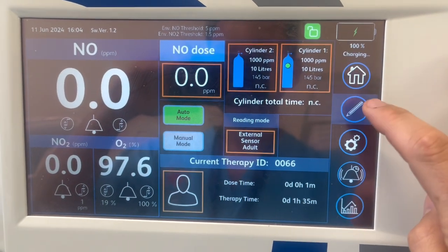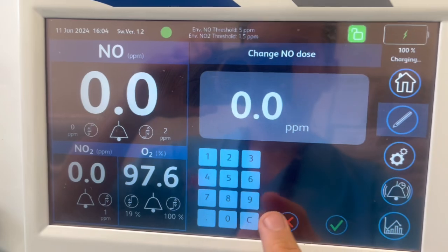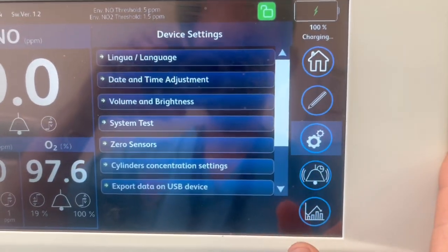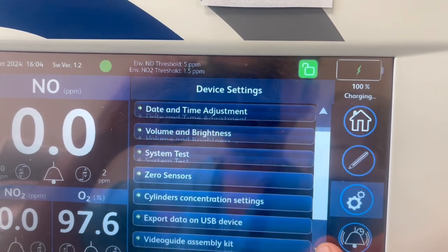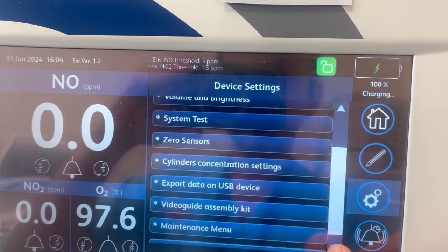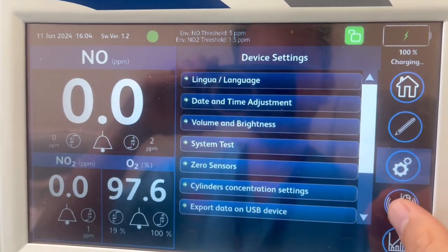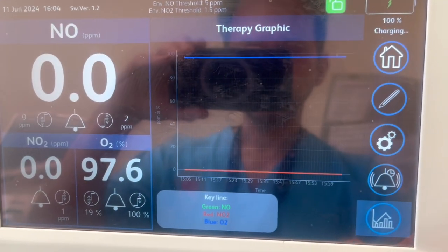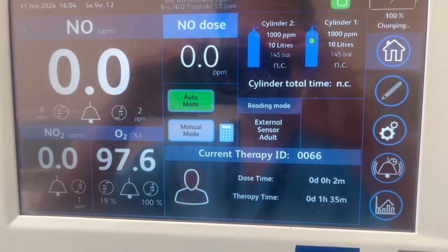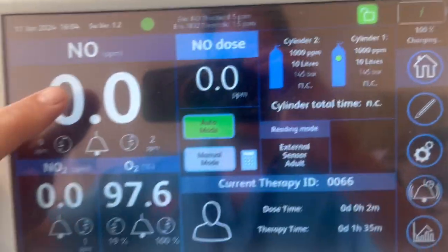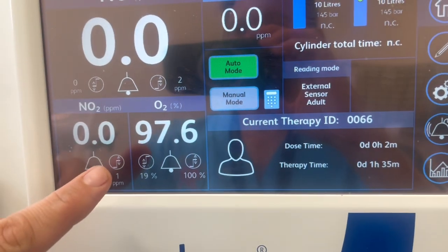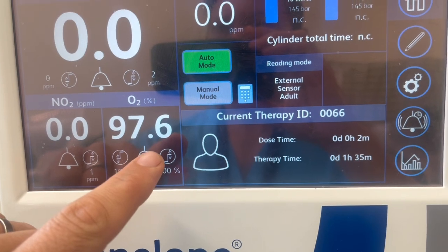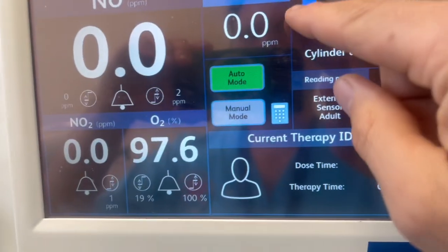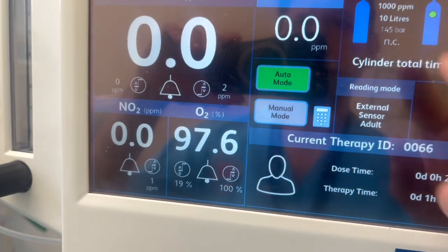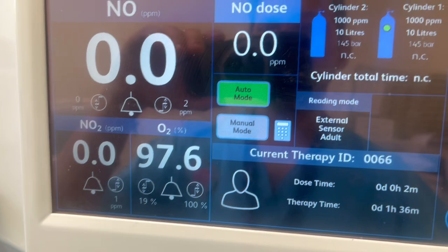The home screen, the pencil icon to change the nitric dose, settings, alarms, and a graphical display of the nitric oxide dose. Here we can see the nitric oxide that the sample line's reading, nitrogen dioxide and oxygen. If you're getting nitrogen dioxide, you need to report this straight away. The nitric oxide dose that's dialed in and the cylinders, which are turned blue because they're turned on.